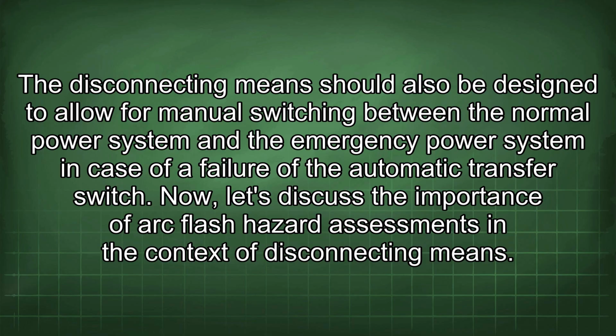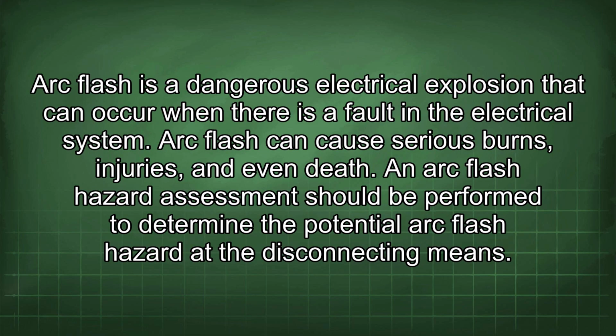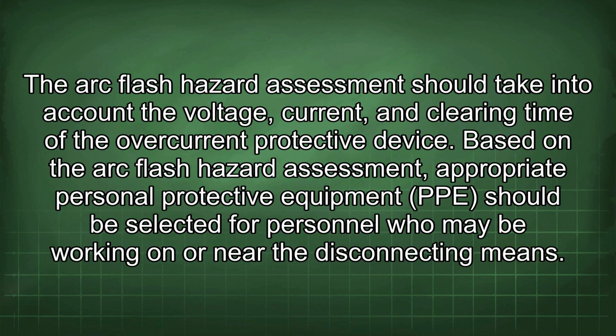Now, let's discuss the importance of arc flash hazard assessments in the context of disconnecting means. Arc flash is a dangerous electrical explosion that can occur when there is a fault in the electrical system. Arc flash can cause serious burns, injuries, and even death. An arc flash hazard assessment should be performed to determine the potential arc flash hazard at the disconnecting means. The arc flash hazard assessment should take into account the voltage, current, and clearing time of the overcurrent protective device. Based on the arc flash hazard assessment, appropriate personal protective equipment (PPE) should be selected for personnel who may be working on or near the disconnecting means.